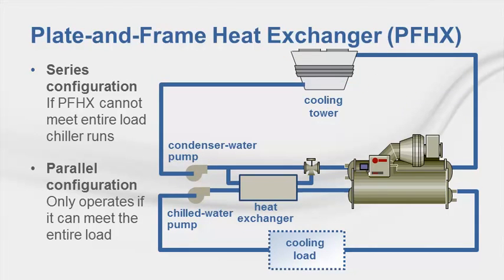Next up, the plate and frame heat exchanger. Now the water loops are isolated, keeping the chilled water loop clean with a slight decrease in heat transfer efficiency due to the heat exchanger itself. The heat exchanger typically requires annual maintenance, adding the expense of cleaning and reassembly, so it's important to include this recurring cost in the lifecycle cost analysis of this option.